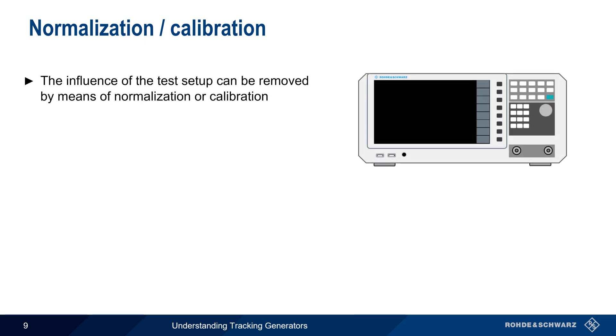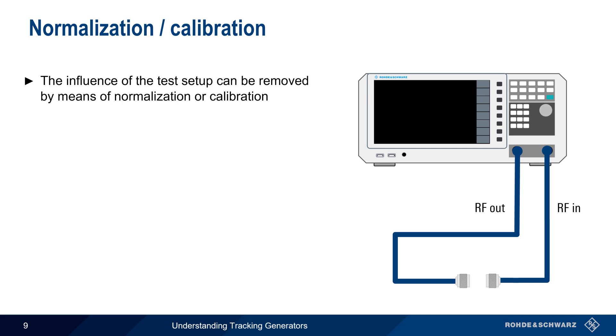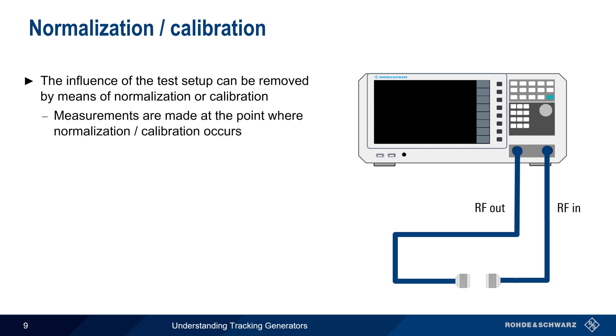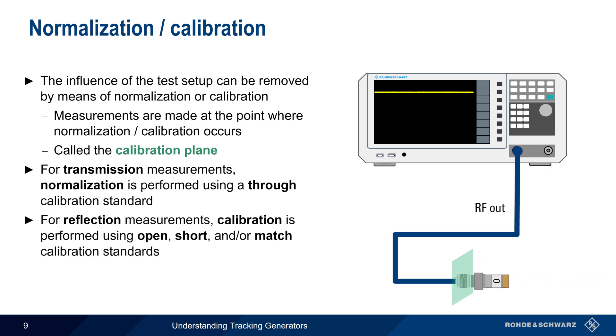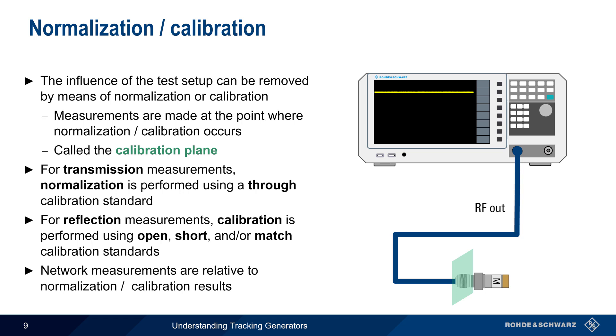Normalization and calibration are important for all network measurements because they can remove the effect or influence of the measurement setup — for example, any cables, connectors, etc. between the device under test and the analyzer. By performing normalization or calibration, measurements are effectively made at the point where normalization or calibration occurs, commonly called the calibration plane. For transmission measurements, normalization is performed by placing a through standard at the measurement point. For reflection or one-port measurements, open, short, and match calibration standards are placed at the connection point. Measurements are then made relative to these normalization or calibration results.